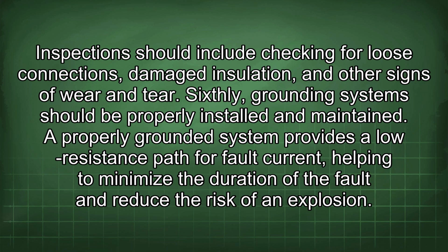Inspection should include checking for loose connections, damaged insulation, and other signs of wear and tear. Sixthly, grounding systems should be properly installed and maintained. A properly grounded system provides a low resistance path for fault current, helping to minimize the duration of the fault and reduce the risk of an explosion.